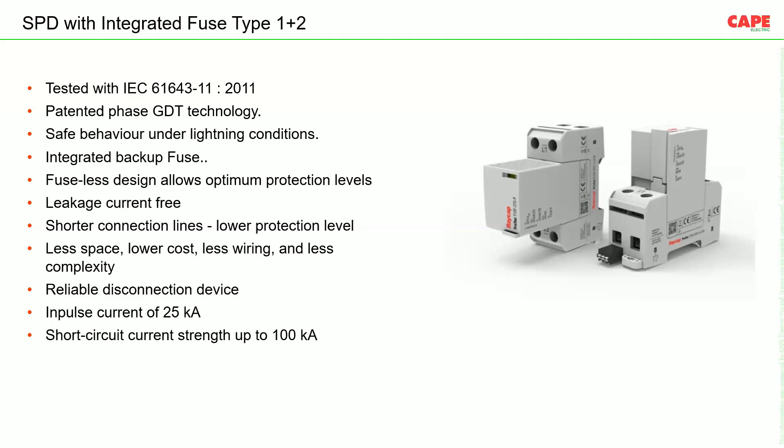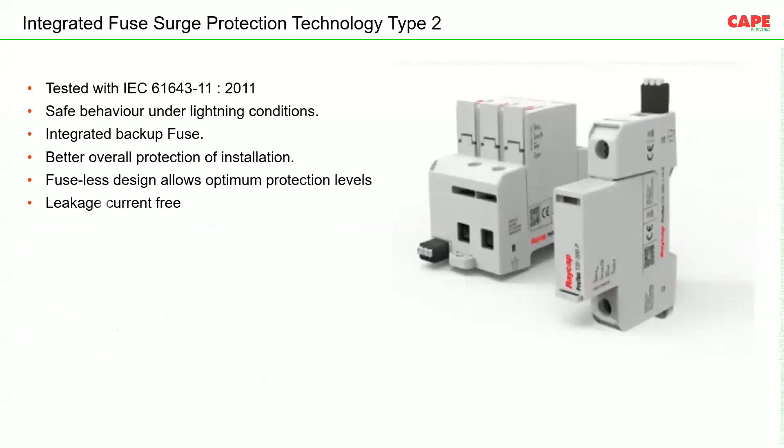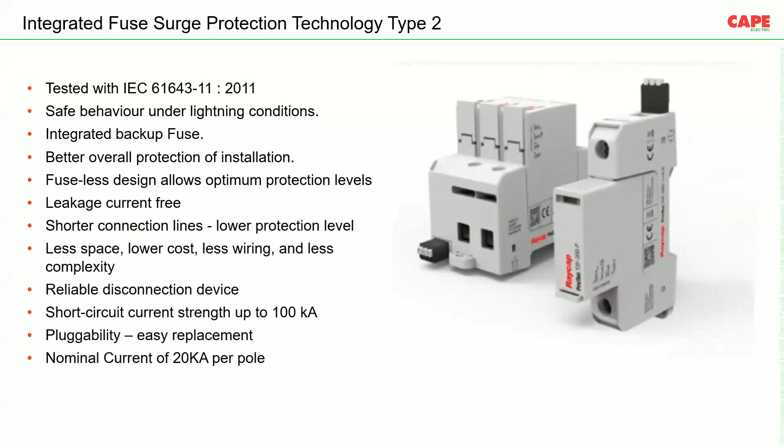This is a Class 1 SPD with an integrated fuse. These are pluggable — if one plug fails, you can easily replace just the plug. There is also a Class 2 SPD with an integrated fuse, which also saves space since there is no separate fuse. It has a nominal current of 20 kA per pole, a short-circuit rating of 100 kA per pole, and a response time of 25 nanoseconds.